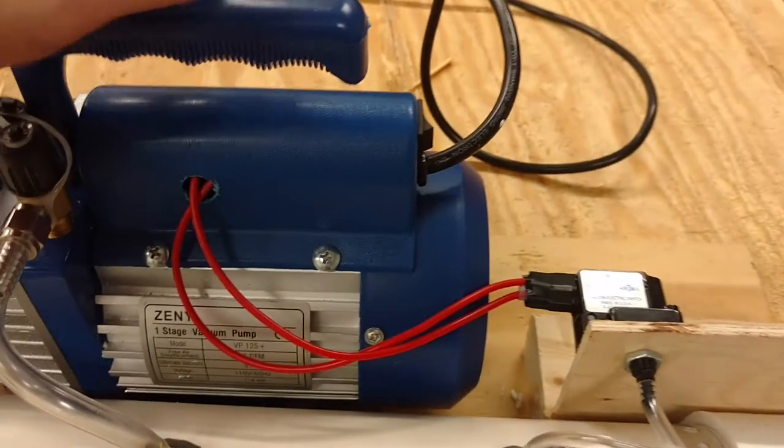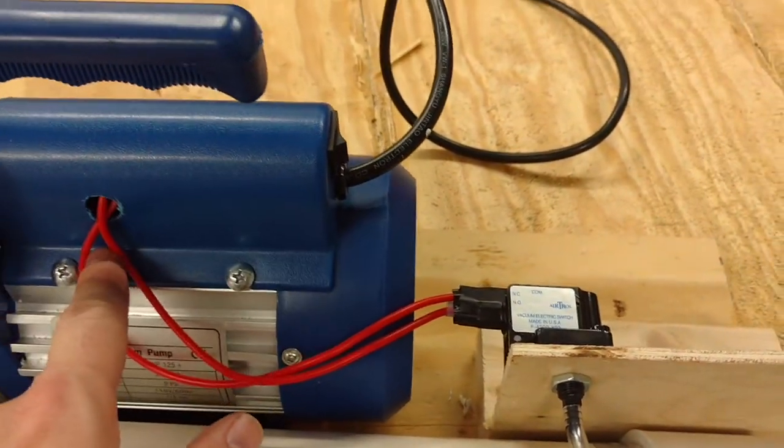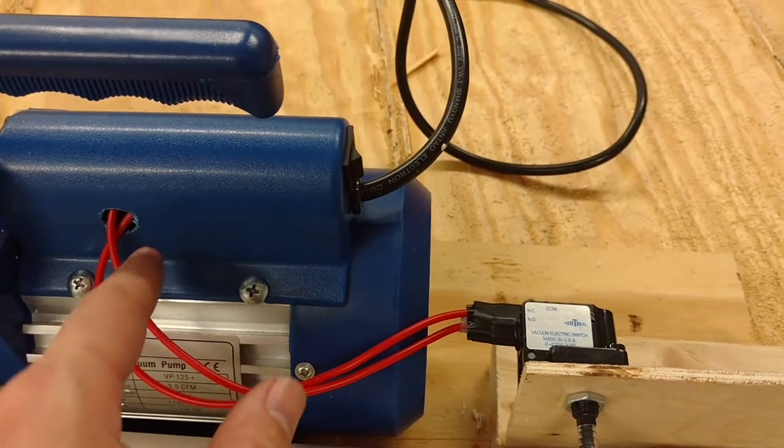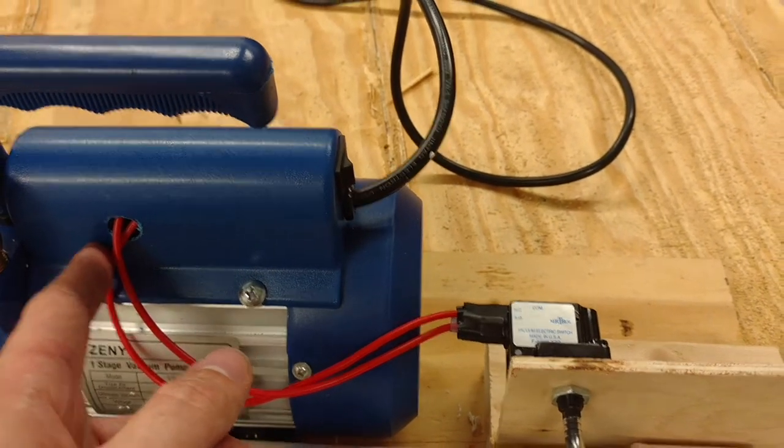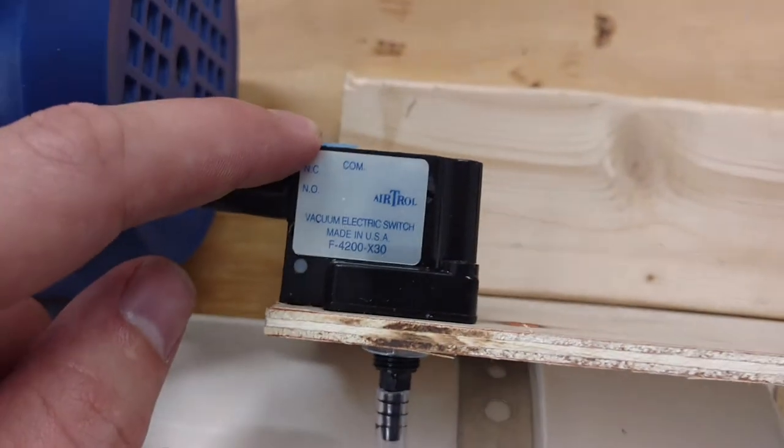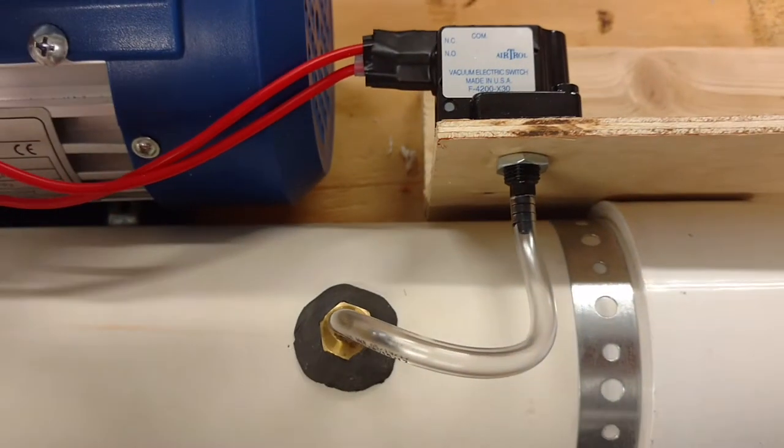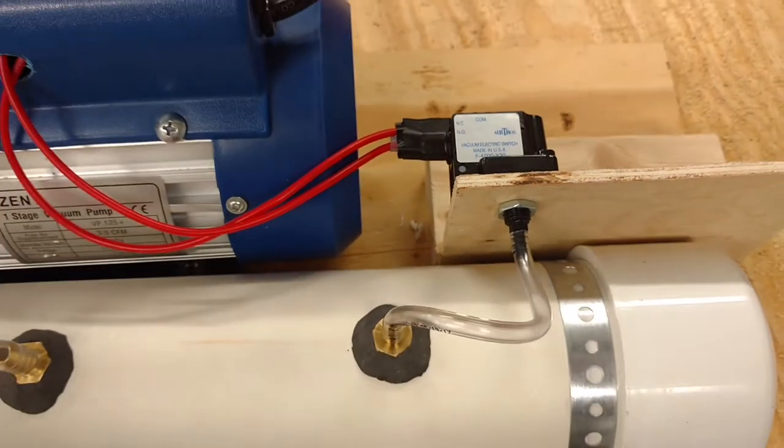To wire this you just pop this cover off and there's a wire that goes to a circuit breaker. You disconnect the one that goes to the line of the circuit breaker from the switch itself over to the common on the vacuum switch. And if it's a normally closed contact you just run that back to the circuit breaker line. So pretty simple, just two wires.